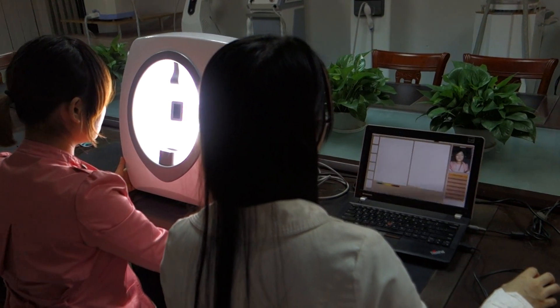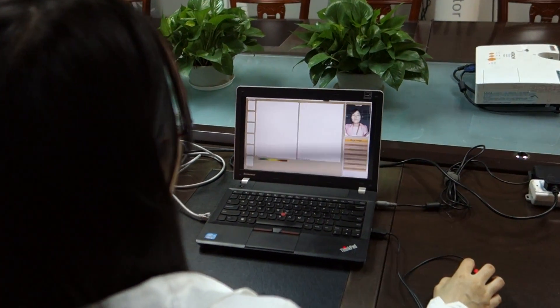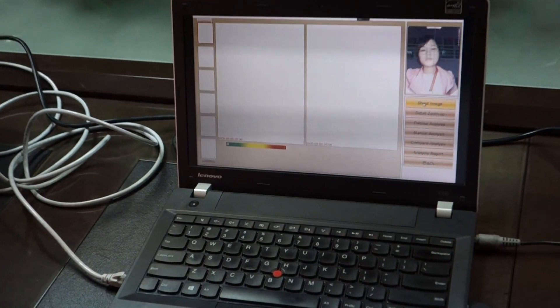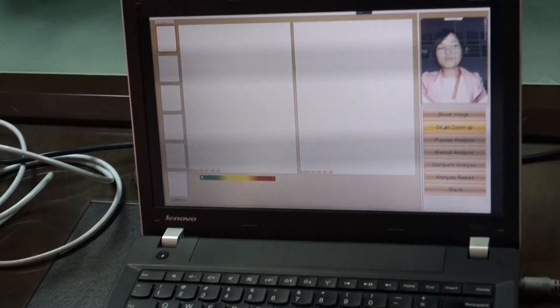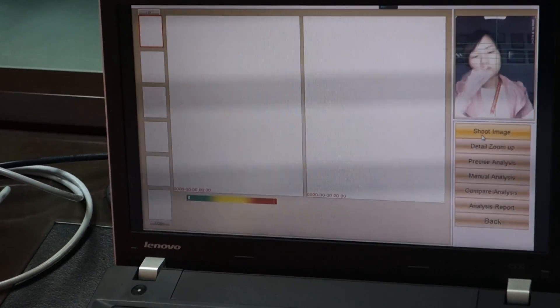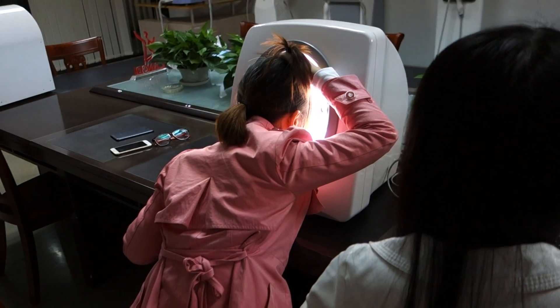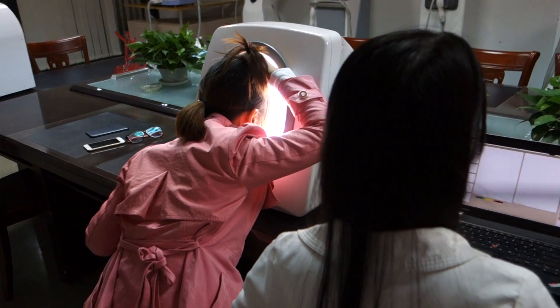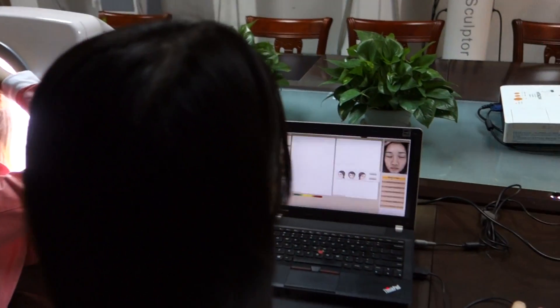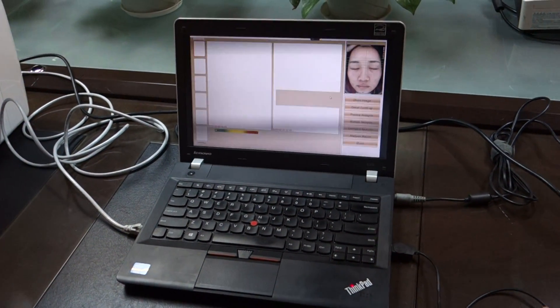It will display 'cannot connect with camera.' Let the customer place her head in the right position and close her eyes and not move. The operator should single click 'Shoot Image,' then single click 'Shoot.' After the light flashes twice, the picture shooting is finished.